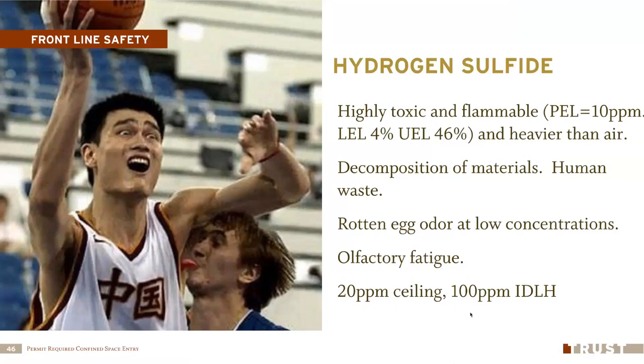It will cause your heart to palpitate, and you'll stop breathing - this stuff will just kill you. It's also flammable as well. 20 parts per million is a ceiling concentration. Your meter will go off at 10 parts per million generally on this, to let you know it's inappropriate to stay in a confined space with hydrogen sulfide.